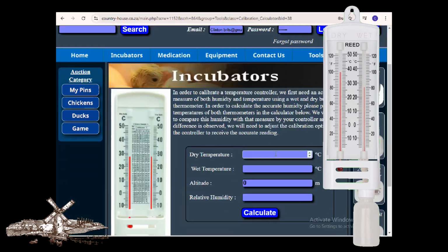So we can see here that my dry thermometer now is showing 37.5 because we in fact calibrated the temperature correctly, and the controller is now maintaining what we expected it to maintain. And so in the first box we're going to type in 37.5 degrees Celsius, and then in the second one, the wet bulb thermometer, you can see is at 27. So we will type in 27 degrees Celsius, and we will then push the calculate button. And you can see that my humidity calculates at 44%. And that is way, way too low.